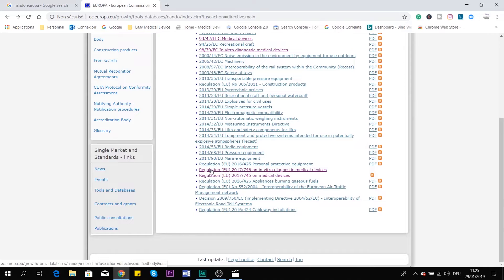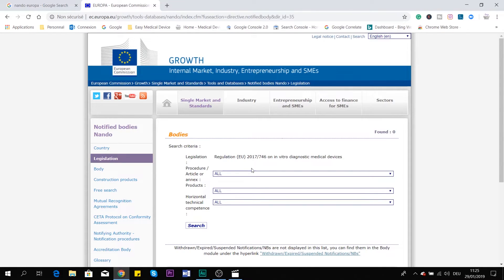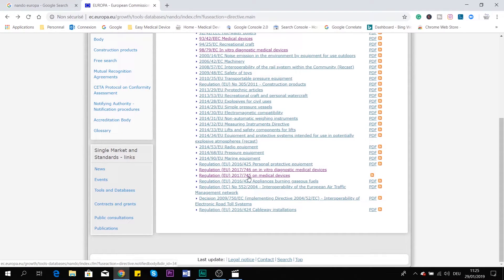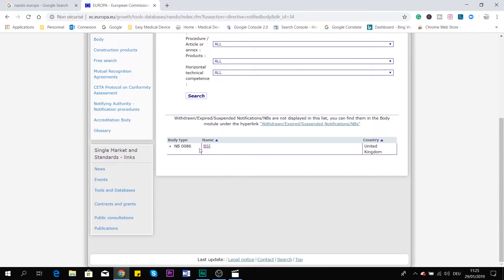We can also check the new Medical Device Regulation and the new In Vitro Diagnostic Regulation. If you want to check which notified body is accredited for the IVDR, you click here — and as of today, end of January 2019, there is nobody yet; they are still under assessment. For the MDR 2017/745 on medical devices, we have been informed recently that BSI is now accredited. The question is, as they are in the United Kingdom, what can they do after March 2019 because of Brexit — the UK would no longer be part of the European Union.